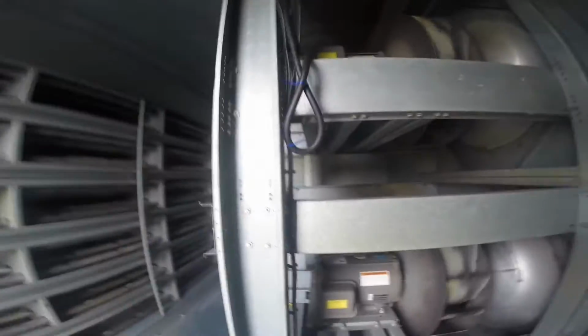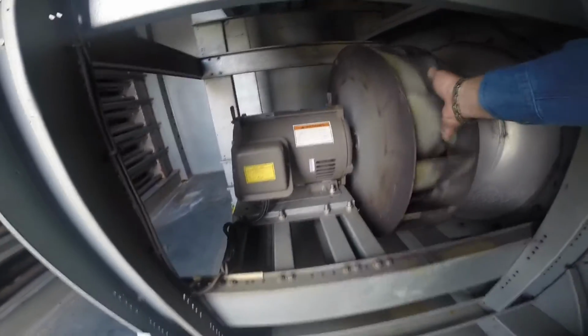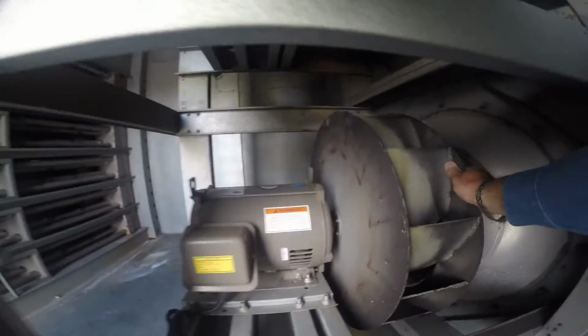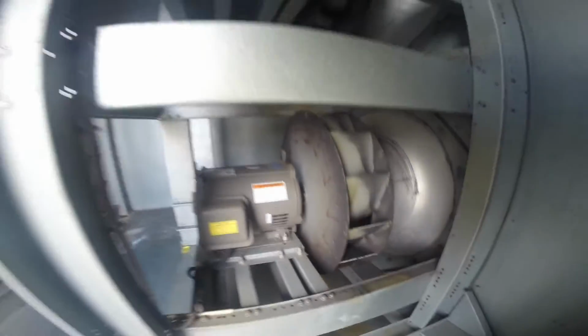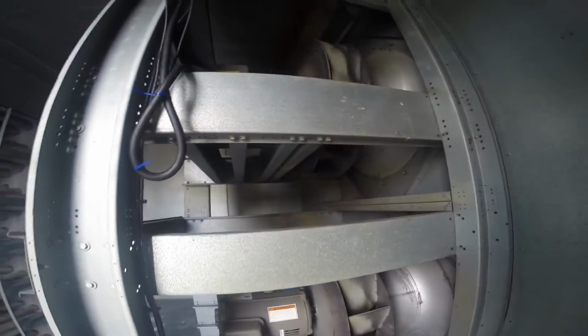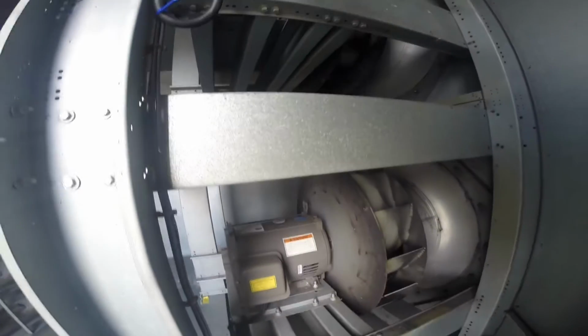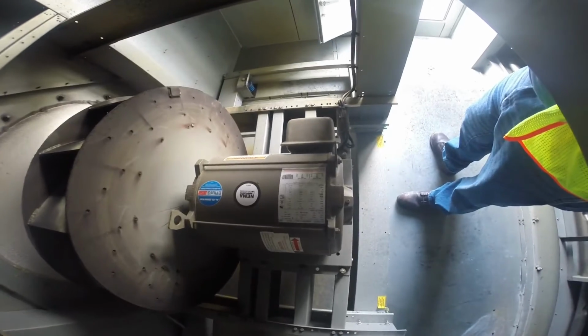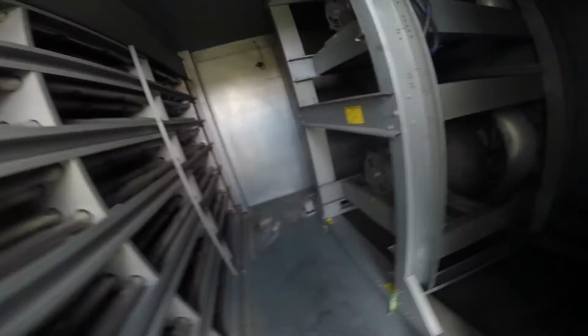For the blower inspections, the upper motor seemed to check out all right, no issues. This bottom blower right here has a bad bearing. That blower motor is going to need to be replaced. Alright, this is the inlet side of the heat exchanger and the blower section.